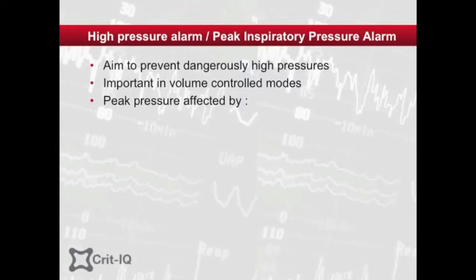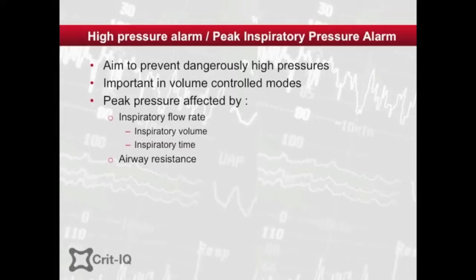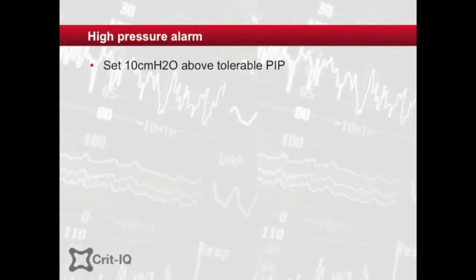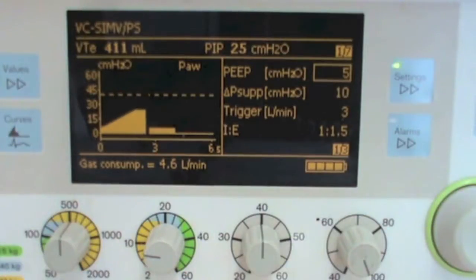Peak pressure is affected by inspiratory flow, which in turn depends on inspiratory volume, inspiratory time, and airway resistance. To a lesser degree, it is affected by lung compliance. The high pressure alarm is usually set within 10 centimetres of water of the desired maximum peak inspiratory pressure, or PIP, and when triggered, the alarm results in automatic cycling of the ventilator into expiration.